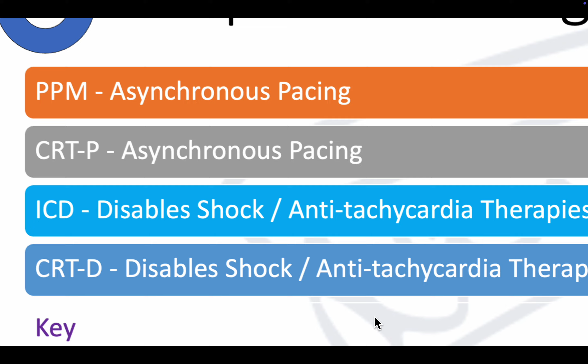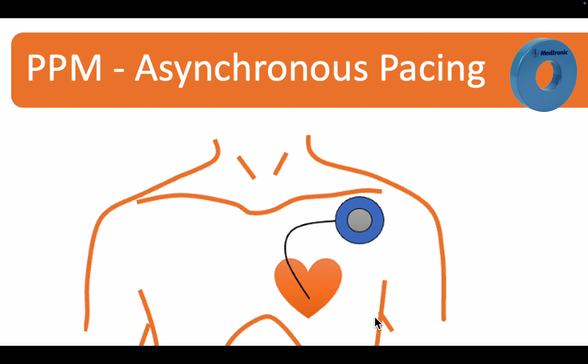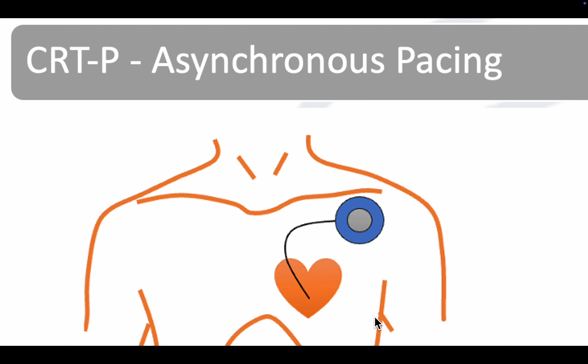The next thing is response to magnet. What happens if you place a magnet over a pacemaker? If it is a permanent pacemaker and you place the magnet over it, it will convert into asynchronous mode. What is important to know is what kind of pacemaker it is. Each pacemaker company advises where to place the magnet. For some, it can be on the lower part of the device; in some, it can be over it; for some, it needs to be placed just over the top of the device. This is because it depends on where the reed switch is situated within the pacemaker device. Again, for CRTP, if you place a magnet, it will convert into asynchronous mode. For the ICD and for the CRTD, it disables the shock or antitachycardia therapies, but the pacing or the CRT is unaffected.